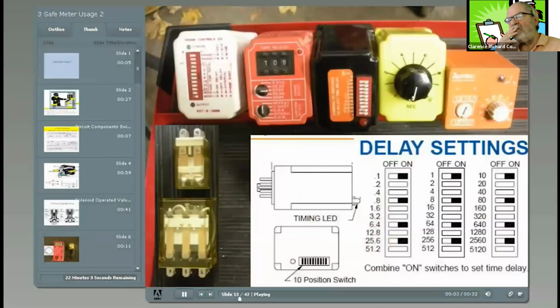Timers are just special relays in that their contacts actuate at different times than normal relays. Relays could almost be considered 0-second time delay relays. These timers have times that can be set with switches and knobs. Some timers are a dedicated type, such as delay on break, delay on make, single shot, etc. Some are so fancy you can pick and choose the type by rotating a knob. For more information, download the timer.pdf.